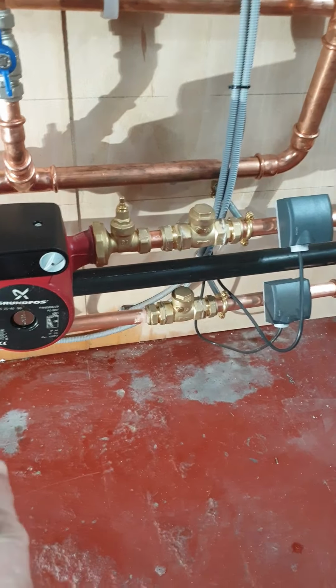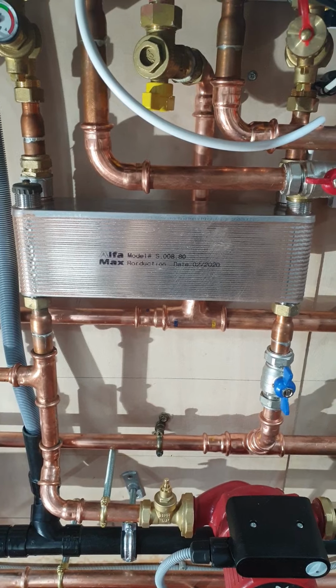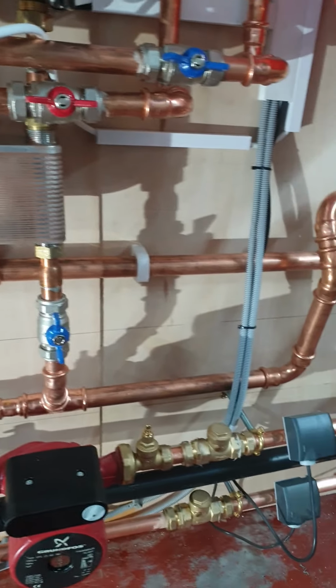These heat exchangers are both 40 kilowatts. The boilers are 32 kilowatts. So that's on LMTD 10. So we should be getting somewhere below 10. So at maximum load, we shouldn't be dropping off too much on our maximum flow temperature.